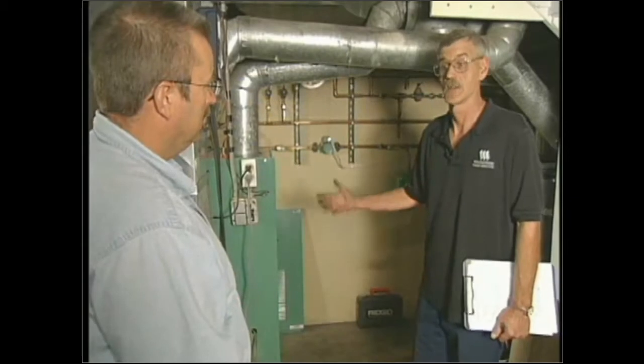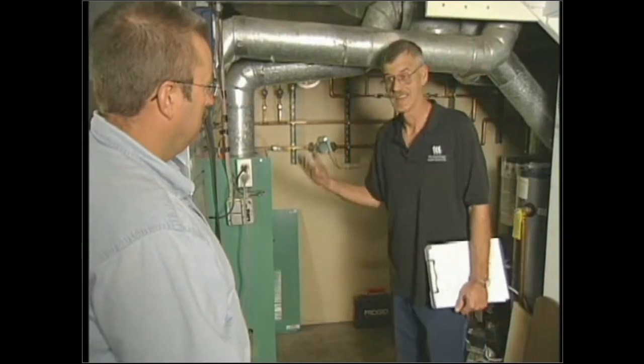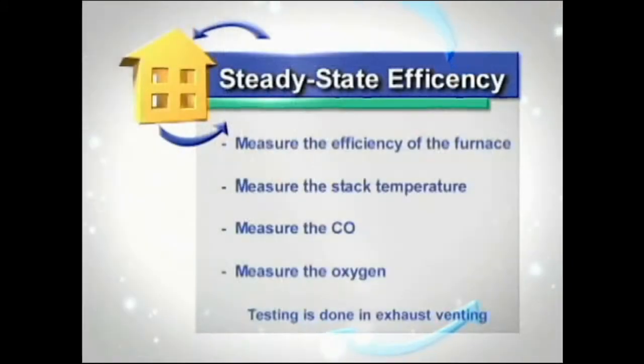Another test that the auditor has to know how to perform is the steady state efficiency test. When we perform that test, what we're trying to measure is the steady state efficiency of the unit. It tells me the stack temperature of the unit, how much CO the unit is producing, and the oxygen content of the air that's being burnt.